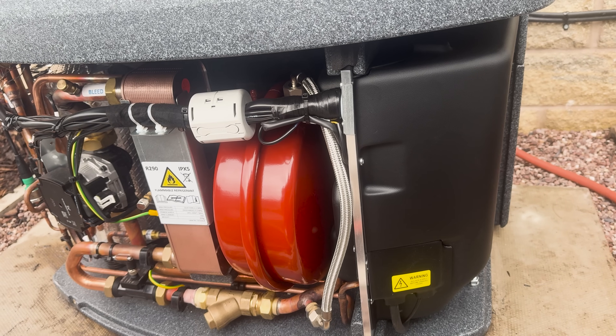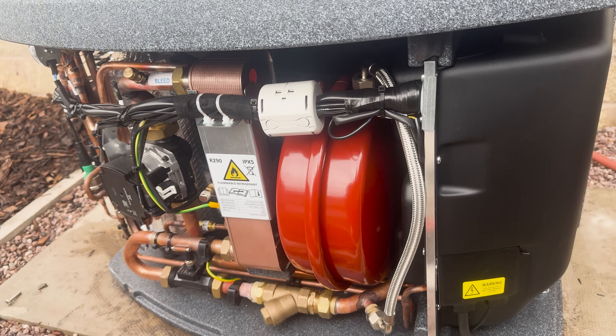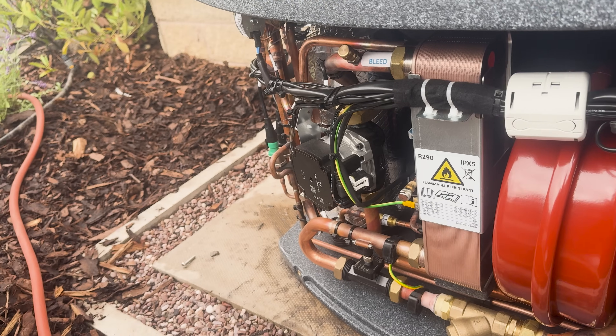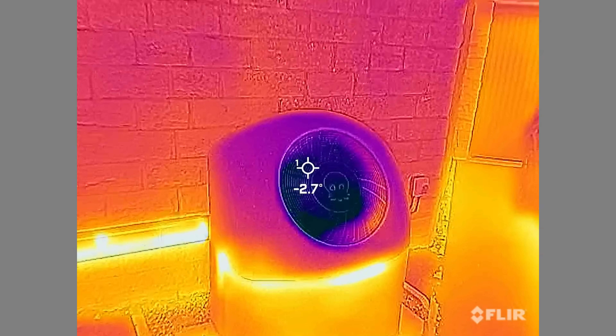We're going to see how well insulated the Cosy 6 heat pump itself is, how well the pipes are insulated, and the bits that Octopus didn't insulate which I've decided to DIY insulate - and we'll talk about whether that's actually worth it at all. Starting with the Cosy 6 unit itself: the pipes inside are not insulated, which is not uncommon for heat pump manufacturers.